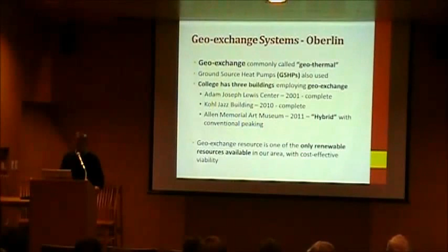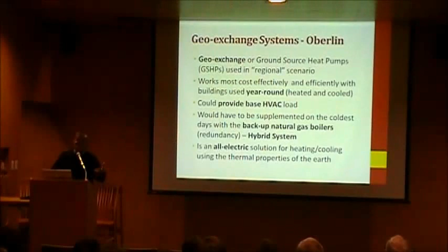It works most effectively on year-round buildings that are both heated and cooled, or if you can group buildings together — as we'll discuss in the regional scenarios — where one group of buildings could be heated in the winter, and you take the cooling load from another building to offset the heating load for the GeoExchange well system in summer, then maybe heat it with conventional means. But it would be an all-electric solution, and we'll talk about why that's a good thing in a minute.